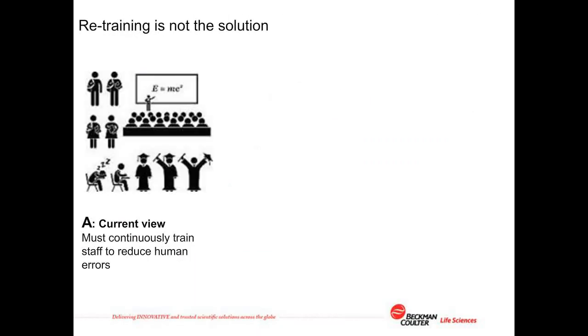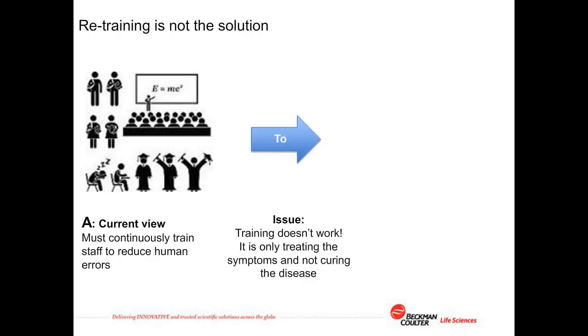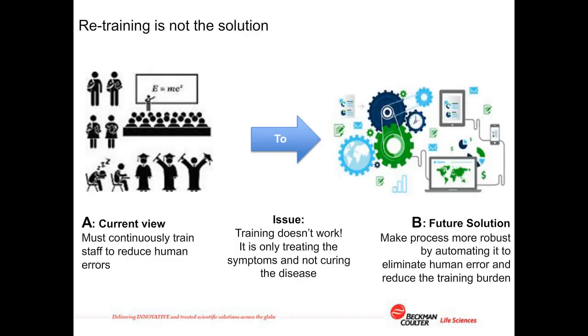This is very much on the FDA's mind. Another common theme is that the FDA is saying retraining is not the solution. Saying the reason we have a problem is because staff need retraining is generally not acceptable to the FDA. They're saying that by retraining, all you're trying to do is treat symptoms and not cure the disease — it only works for a short period until human error starts to creep in again. What they're really suggesting is the correct way forward is to make the process more robust. If we can automate it to eliminate those human error steps, that will make it more reliable and robust, and reduce the training burden in the industry as well.